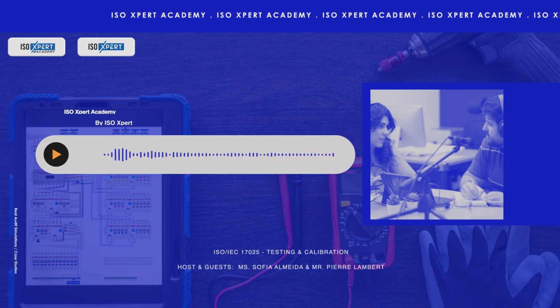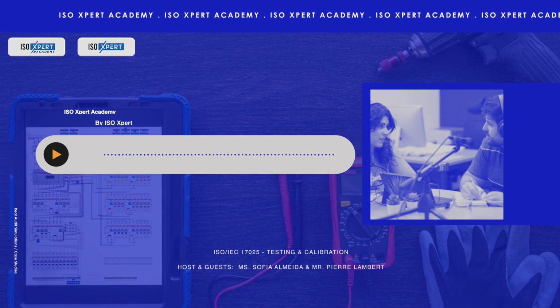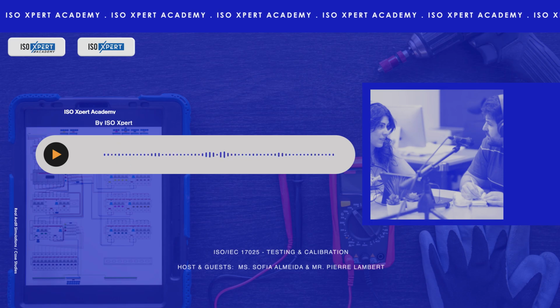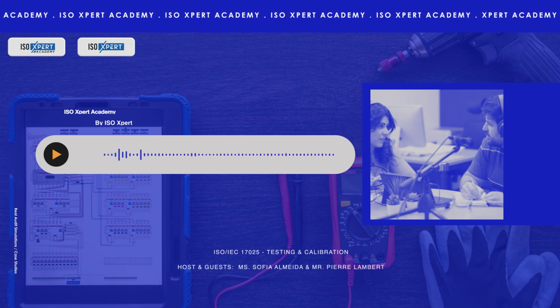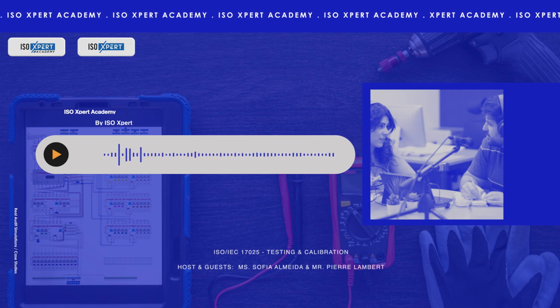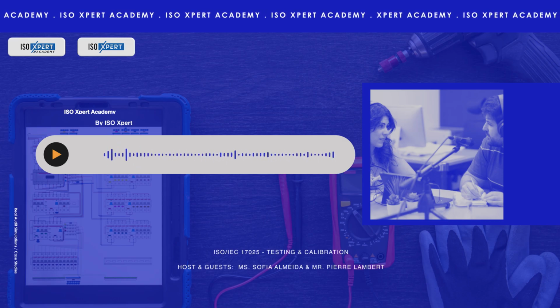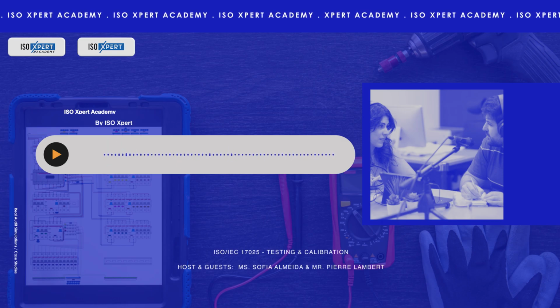Yeah, this links back to that uncertainty issue, actually. The auditors looked at the temperature log for one of the calibration rooms. It showed occasional temperature readings that went slightly outside the acceptable range. The target was 23 degrees C, plus or minus 2 degrees C, and sometimes it drifted beyond that. Even small drifts can matter for high-precision work, right? They really can, especially over time.